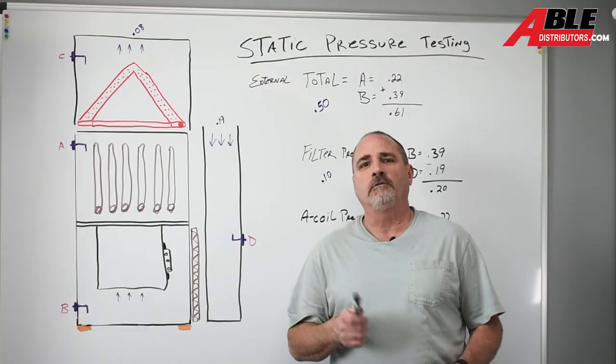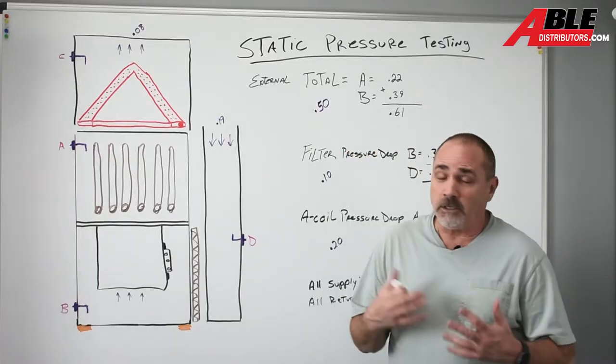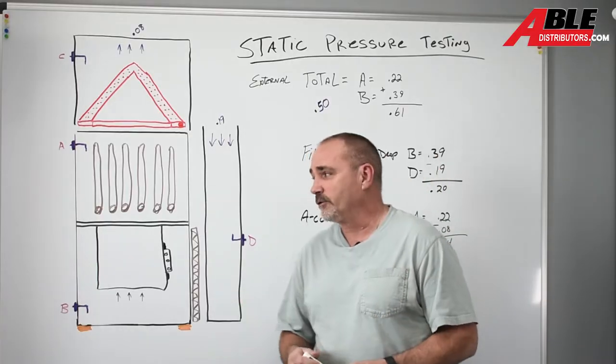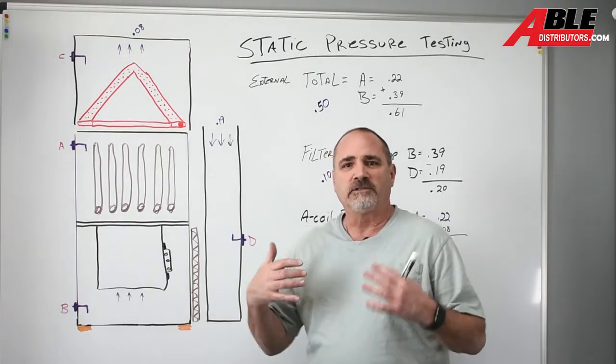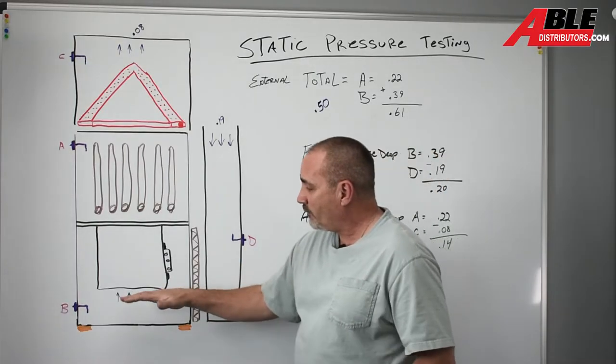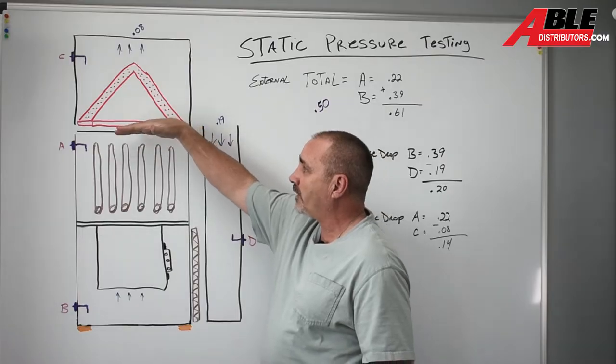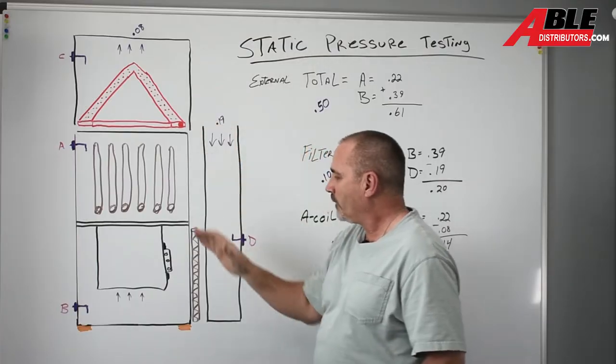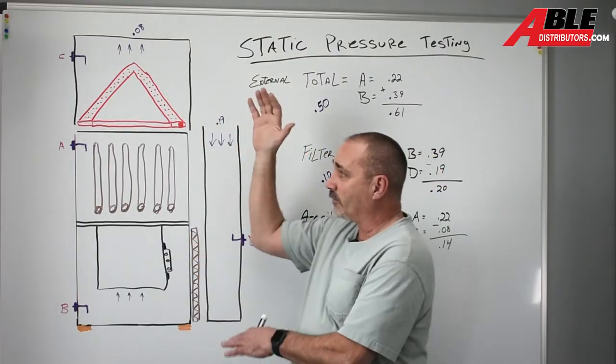Today I wanted to talk to you about static pressure. It's something that we all need to know, we need to check, but very few contractors actually do it. So typically we start at total external static pressure, and by external what we're talking about is everything outside the furnace. Everything on the supply duct from the top of the furnace away and everything from the side of the furnace away on the return duct. Everything outside the furnace.